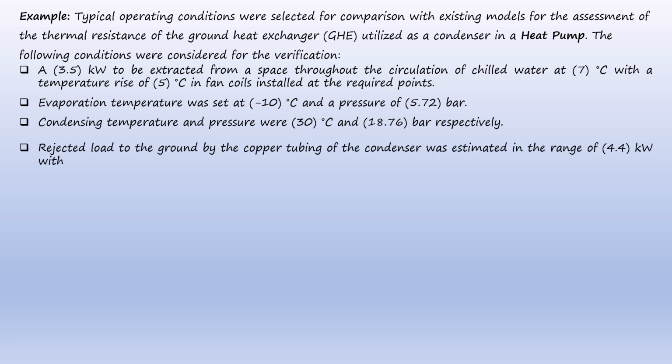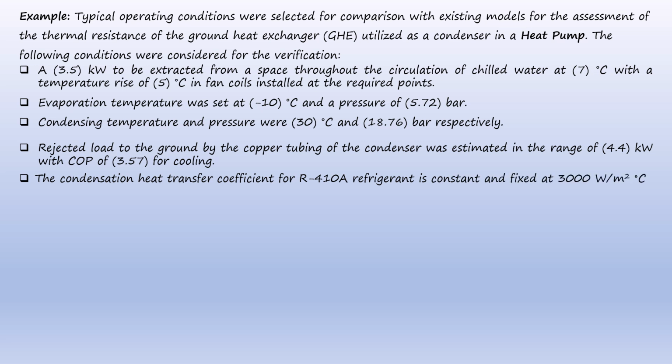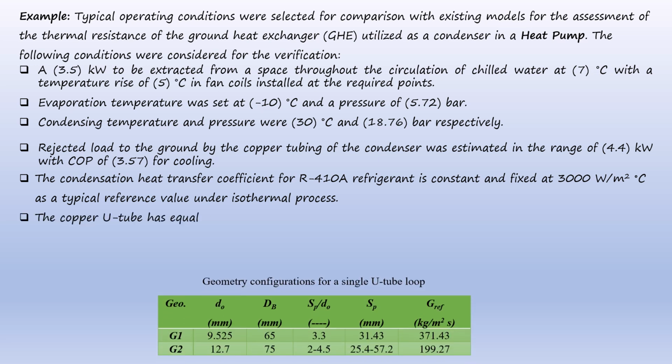The rejected load was estimated to be around 4.4 kilowatt with a COP of this heat pump of 3.57 for cooling. And the condensation heat transfer coefficient has been used as a typical value for this refrigerant, 3000 watt per meter degree centigrade.